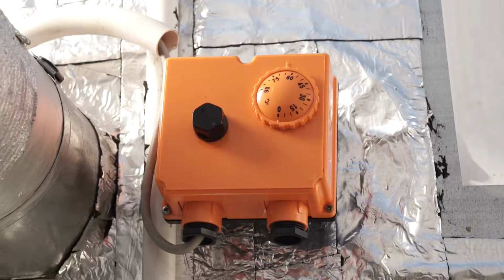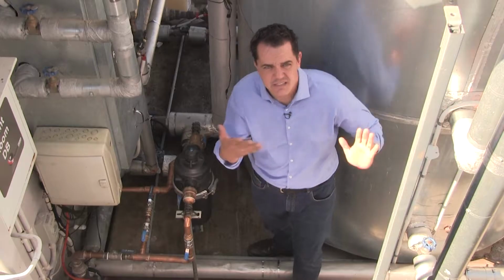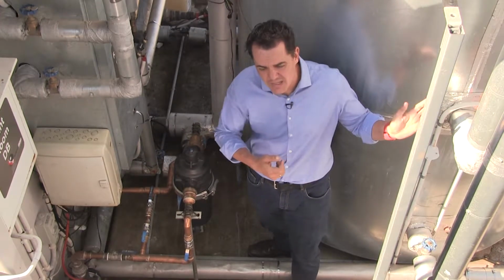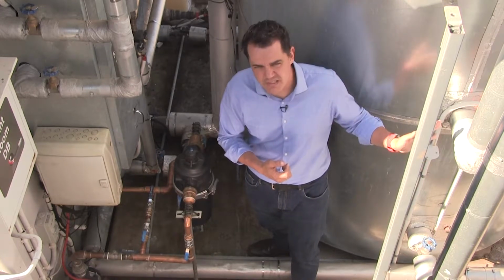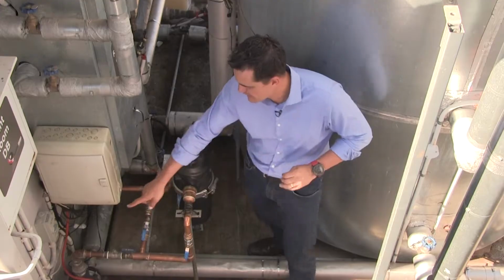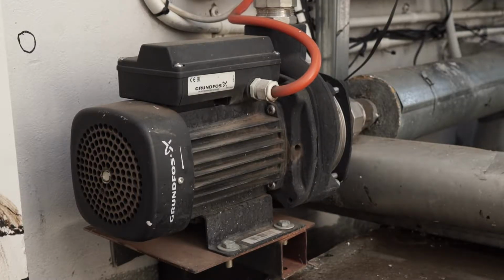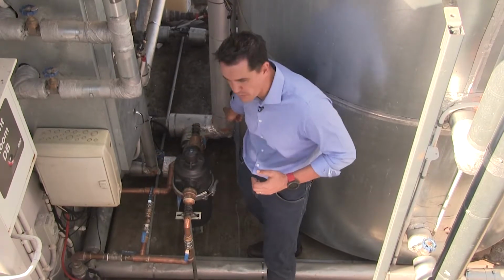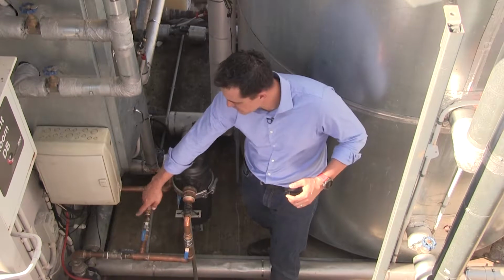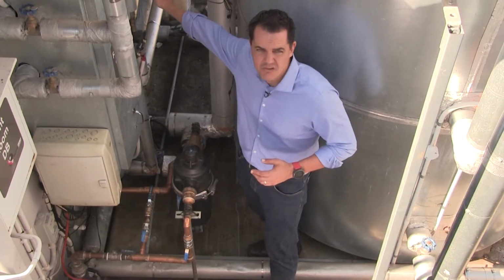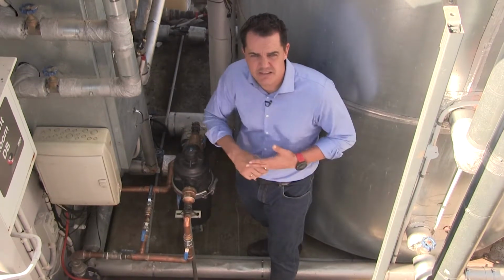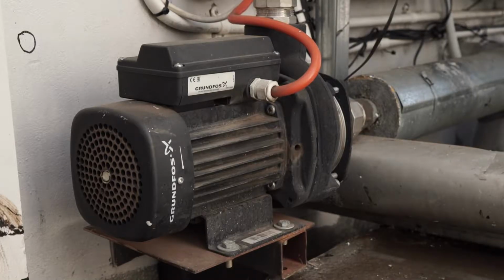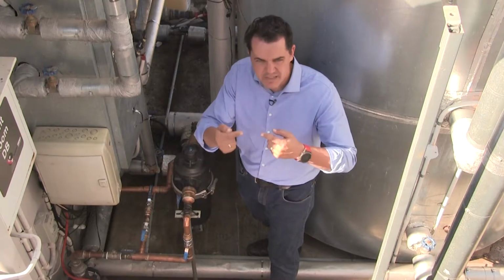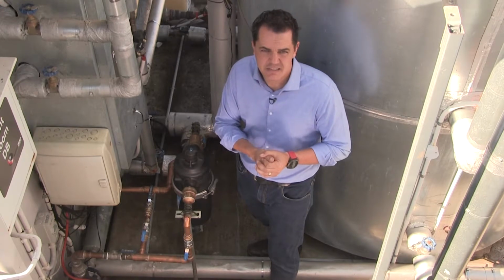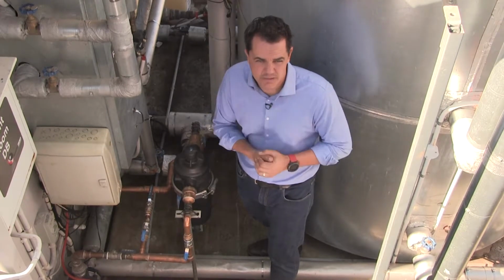We've got a thermostat that's positioned halfway on the tank, and that thermostat is set at 60 or 65 degrees. If the tank goes below that temperature, the thermostat then activates and gives power to the pump. This is our circulation pump, and it circulates water from the bottom of the tank, the cold side, through the pump, through the filter, towards the Rinnai burners. The Rinnai burners are switched on the moment that there's flow. So the thermostat switches on the pump, which circulates water through the Rinnai burners, and the moment there's flow through the burners, they electronically ignite, switch on, and heat the water that's circulated.